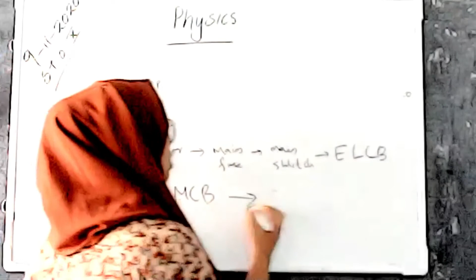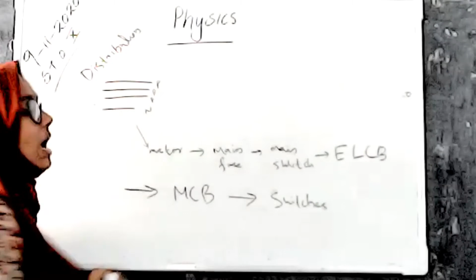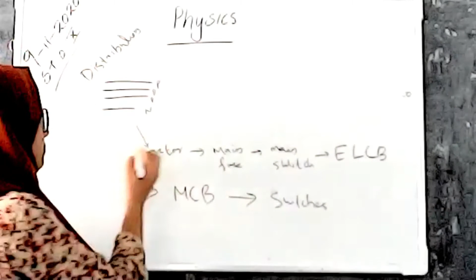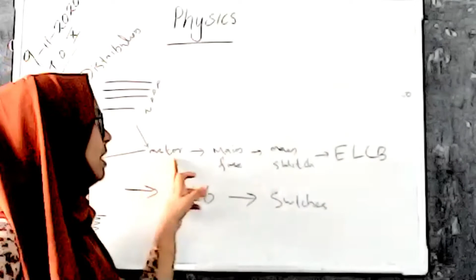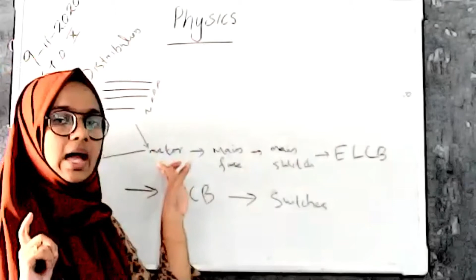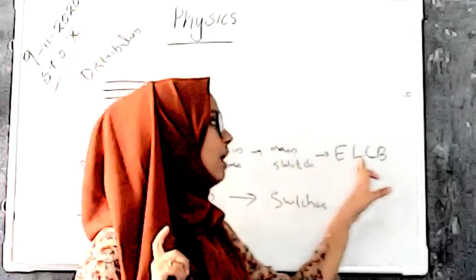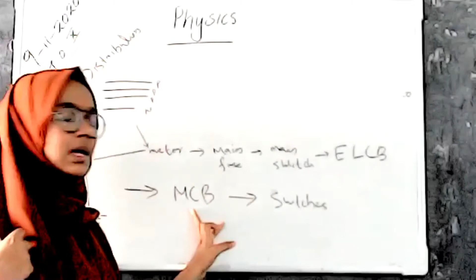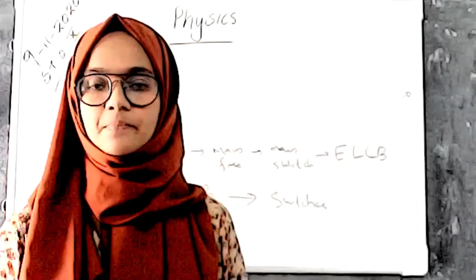So this is the flow of electricity from a distribution transformer to our household uses. It comes from the distribution transformer, which has 4 wires, and those 4 wires connect to the meter. And from the meter, one wire goes to earthing, and the other wires, one phase and one neutral line, are connected to the meter, and it goes to the main fuse, and to the main switch, and the safety measure ELCB, and then again to the MCB, and last it comes to the operating switches. So this is the way electricity flows from the distribution transformer to our household works.